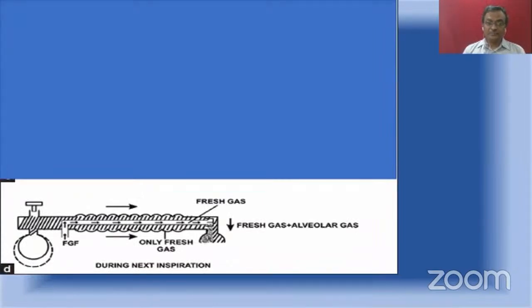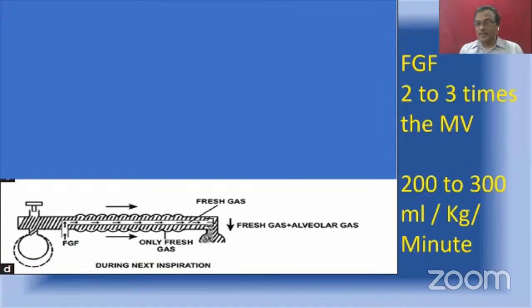So next inspiration, see, some of the alveolar gas will invariably be pushed back to the patient's lung. When you squeeze the bag, the alveolar gas which is collected in the outer tube will be pushed back to the patient. So what the patient inspires is a combination of fresh gas and alveolar gas. So that again depends upon the fresh gas flow rate. If the fresh gas flow rate is low, the patient is going to inhale more alveolar gas, and if it is high, the patient is going to inhale less alveolar gas. So I said already, the fresh gas flow requirement during spontaneous breathing with a Bain circuit is around 2 to 3 times the minute ventilation.